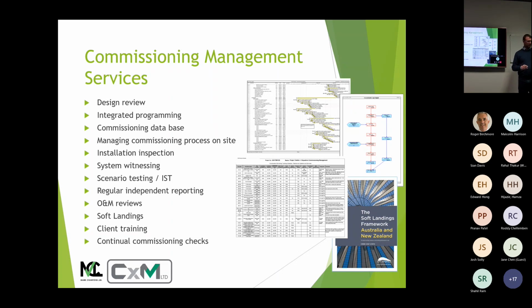Scenario testing is trying to break the system. That's more for mission critical systems, such as a data center or a hospital, where you've got standby systems. Let's get it running, turn off one of those devices, and see the standby device come on and take over, the alarms come up, and ideally the conditions remain within the correct tolerances. Let's turn the power off, make sure the generator starts up and everything switches over. All of those sort of tests.